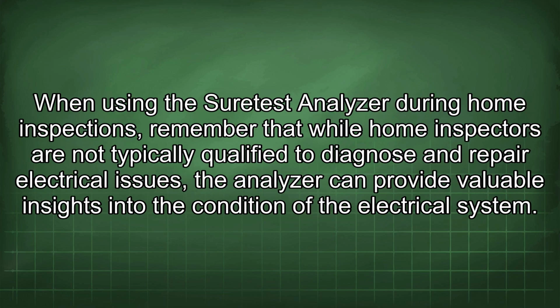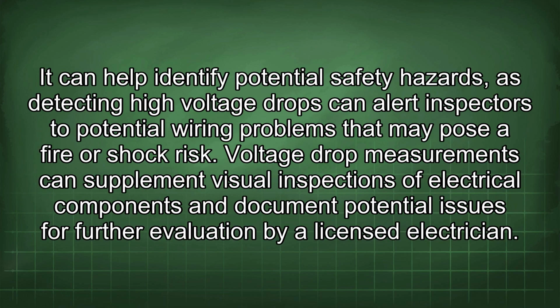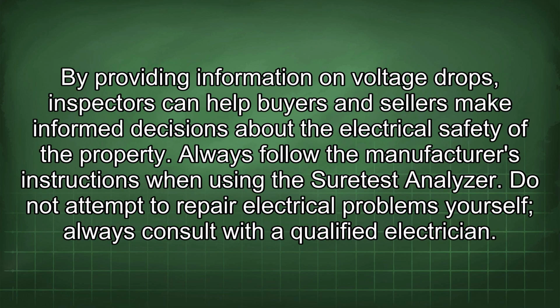When using the Suretest Analyzer during home inspections, remember that while home inspectors are not typically qualified to diagnose and repair electrical issues, the analyzer can provide valuable insights into the condition of the electrical system. It can help identify potential safety hazards, as detecting high voltage drops can alert inspectors to potential wiring problems that may pose a fire or shock risk. Voltage drop measurements can supplement visual inspections of electrical components and document potential issues for further evaluation by a licensed electrician. By providing information on voltage drops, inspectors can help buyers and sellers make informed decisions about the electrical safety of the property.